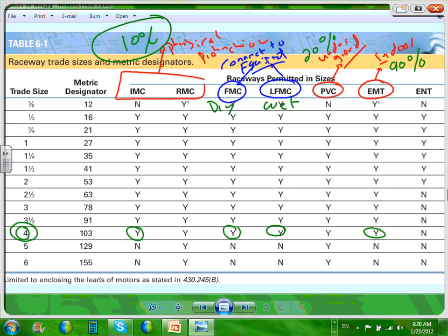Now this is where rigid becomes superior, as well as PVC. Can you guys see where rigid and PVC become superior? Here's an application where I must use rigid. For example, what if I need a size 5-inch conduit to pull my feeders? Do they make 5-inch conduit EMT? No. So what's your only option?